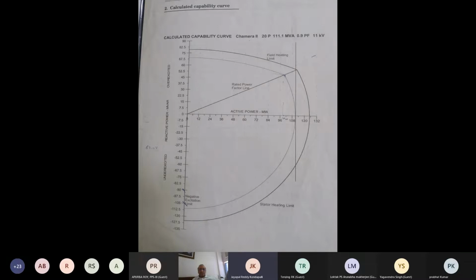So, sir, according to this curve, in what range can I operate the machine? That is what is given on the x and y axis, no? Within this curve, you can operate at any point, as required by the grid, within the capability curve for MW as well as MVAR. As I was mentioning, sometimes when the grid condition is critical, you need to give voltage support to the grid with more reactive power, and in that case you may have to back down active power so that more reactive power can be supplied. So you can operate at any point within the capability curve. Okay. Thank you.